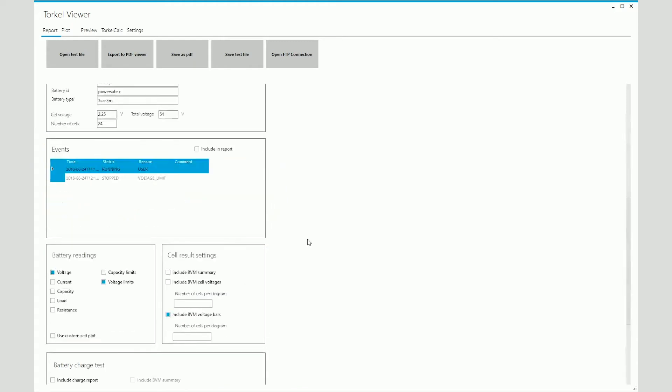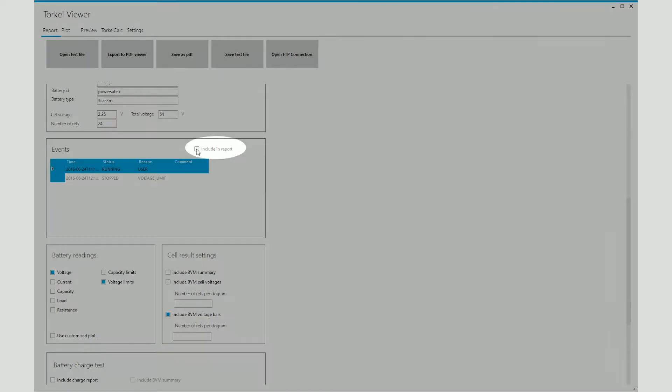After that, you have events. Events is basically a log which details what happened during the test. This test ran pretty normally. It was started and then it stopped when the voltage limit was exceeded. So not too many events here. You can include this log in your report by clicking on this checkbox.